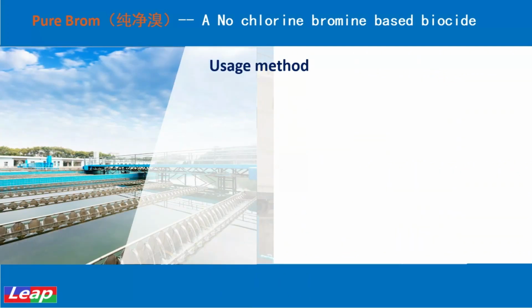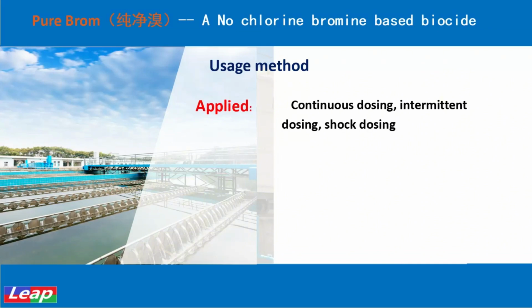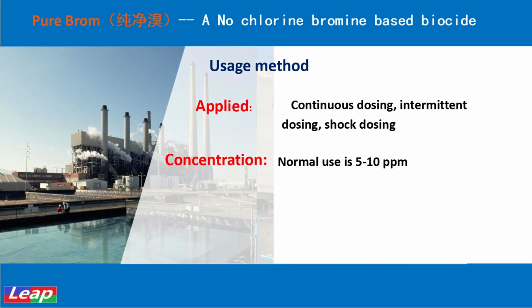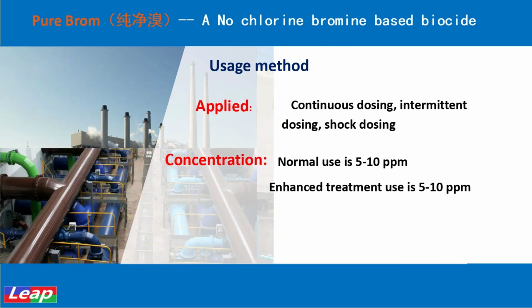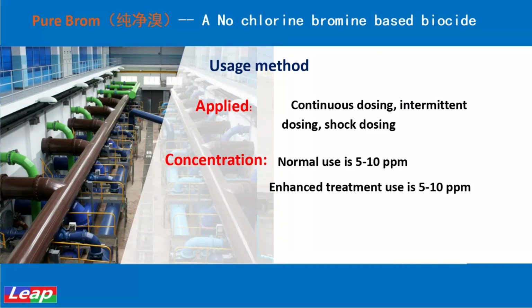How to use Pure Brom. Pure Brom, bromine-based biocide can be applied by continuous dosing, intermittent dosing, or shock dosing. The recommended dosing concentration during normal use is 5 to 10 ppm. For systems already affected by microbial contamination, enhanced treatment can be conducted once or multiple times at a dosing concentration of 10 to 50 ppm.